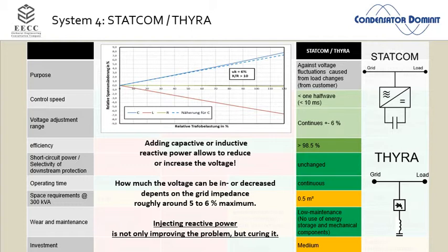Now, if I have such a situation, with 1 megawatt inductive load, my voltage drop behind a transformer with a UK of 6% is more or less 6%. It also depends on the grid before, but it's more or less the UK of the transformer. 1 MVA reactive power behind a 1 MVA transformer with a short circuit voltage of 6%, the voltage drops 6%. That's it. If I put in the same place not an inductive load but a capacitor bank, I can raise my voltage, because my capacitive load has exactly the opposite phase angle to an inductive load. So I raise my voltage, again more or less by 6%. With a capacitor bank of 1 MVA behind a 1 MVA transformer, I can raise my voltage by 6%. And that's it. That's the limitation of pushing in reactive power.